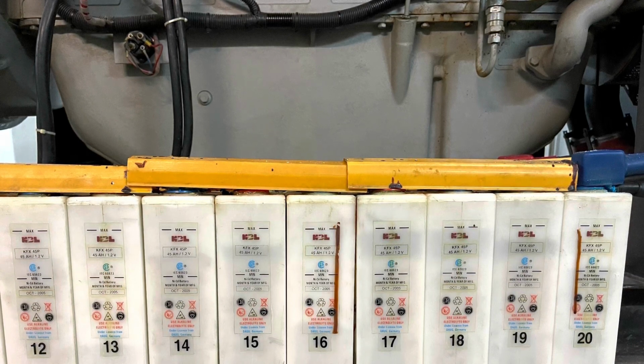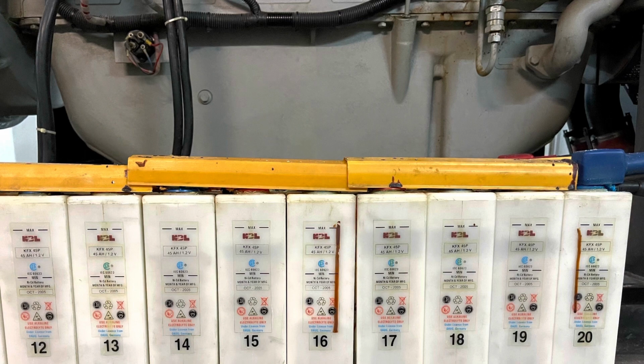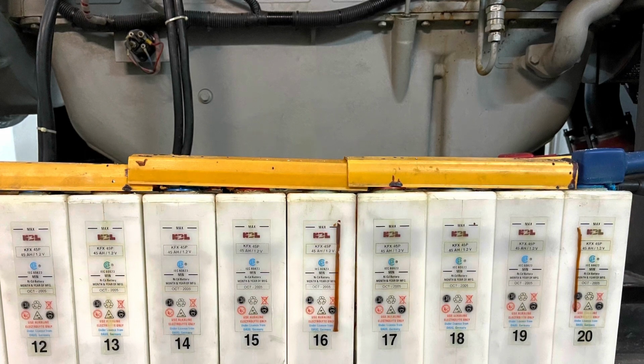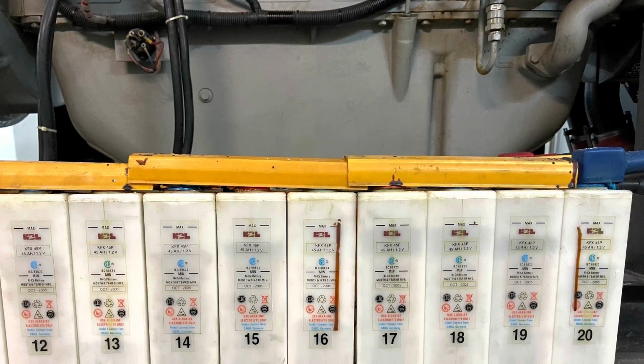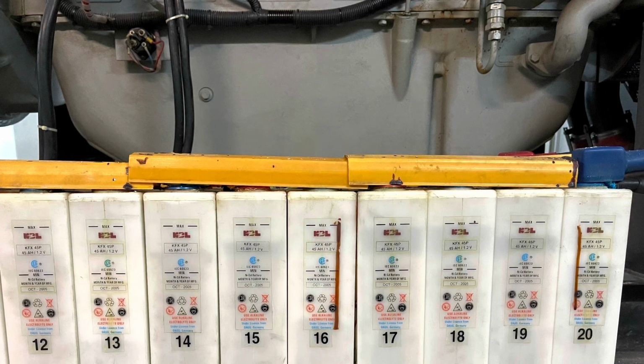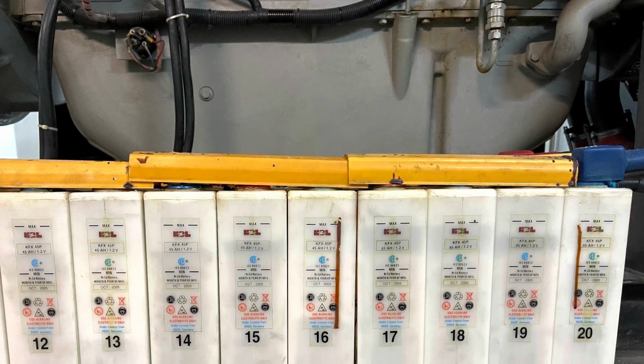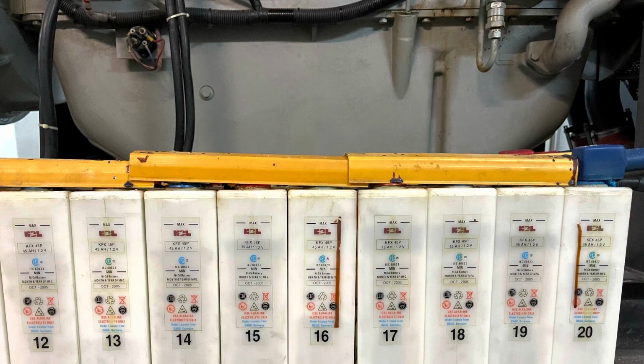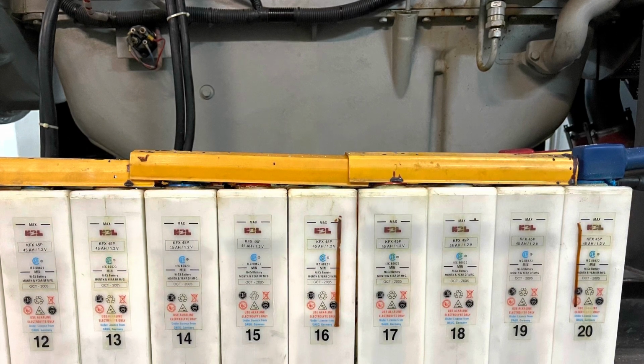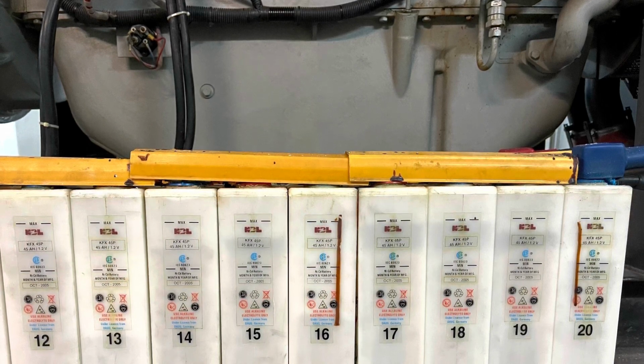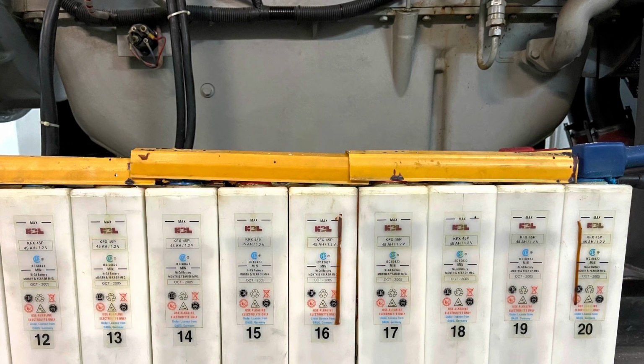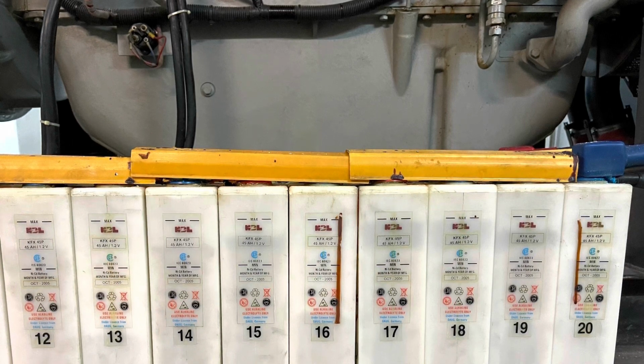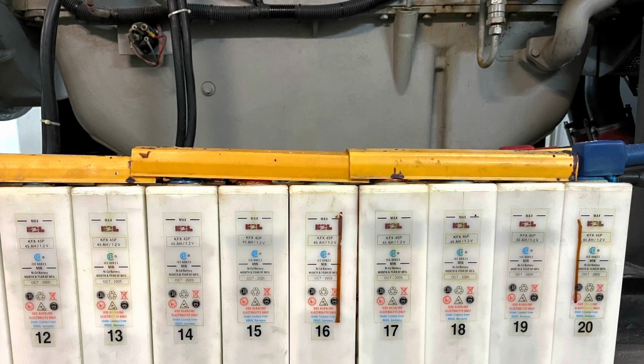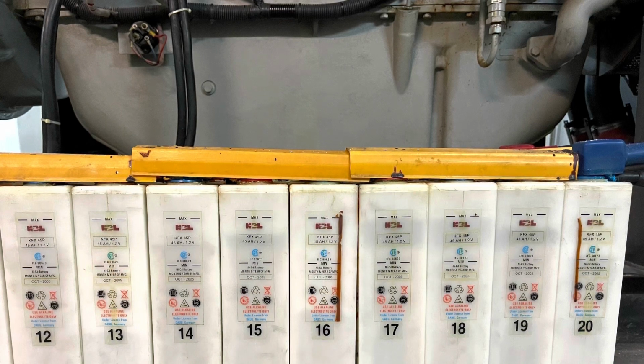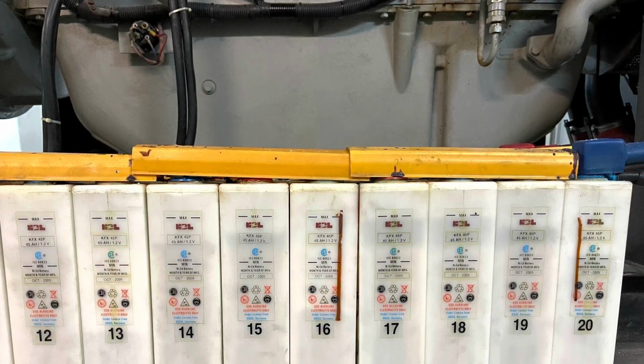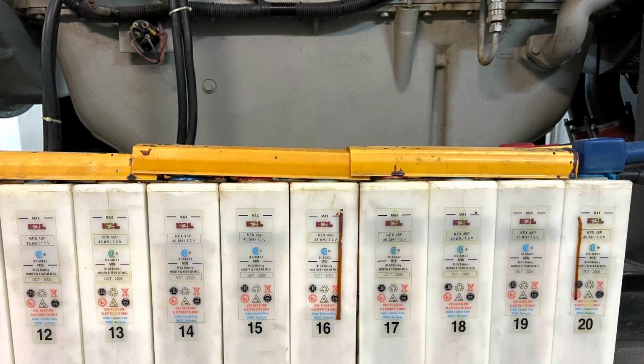Okay, as your voltage drop gets near the 15 volt DC area, and maybe slightly goes lower, it is recommended to replace the battery rather than waiting for it to break down. Then during a TNB power interruption, your genset won't be able to start automatically. Then you'll be in panic, and if you have a lift with no power supply, then you have a man trap.